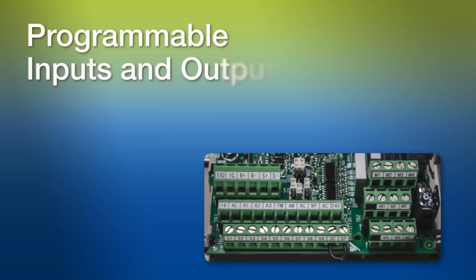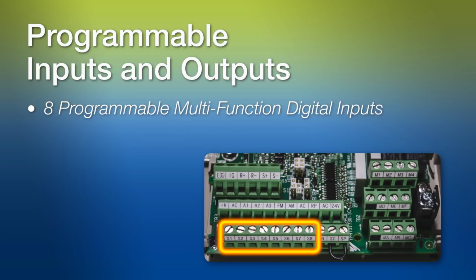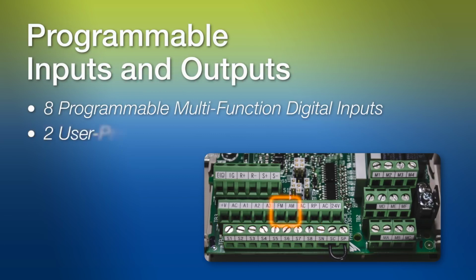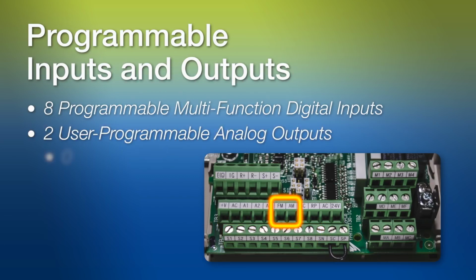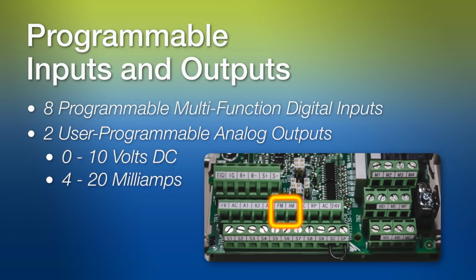A wide array of programmable inputs and outputs are available for even the most demanding applications. The Z1000U has 8 fully programmable multifunction digital inputs. The Z1000U also includes 2 user-programmable analog outputs, which can be set up to output either 0 to 10 volts DC or 4 to 20 milliamps. The outputs are perfect for providing real-time feedback to a building automation system about drive conditions, such as output speed and motor current.